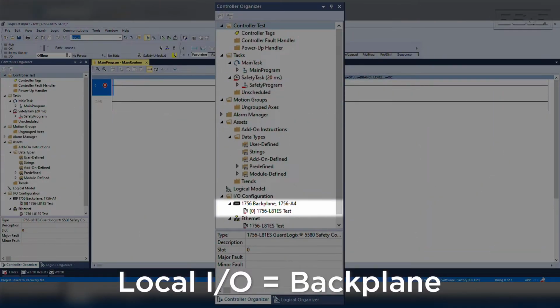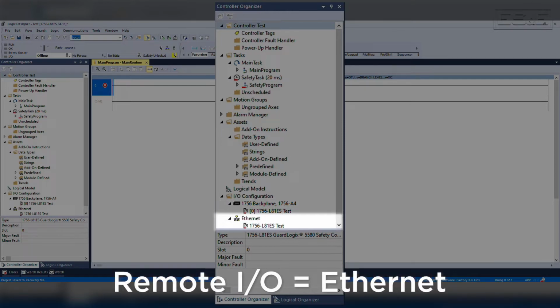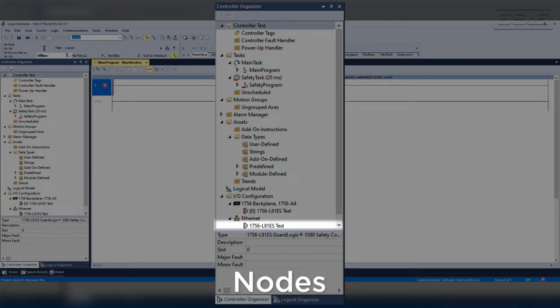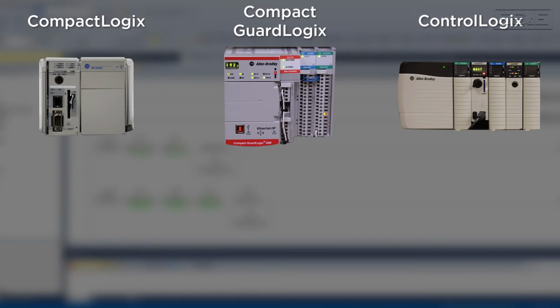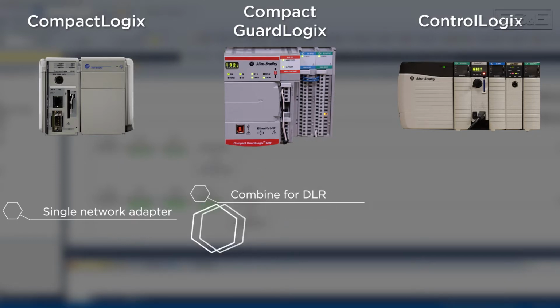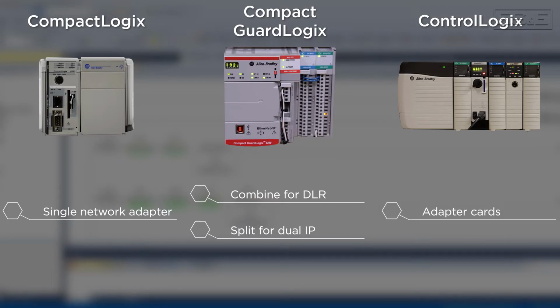Local I/O will always be shown directly connected to the backplane of the controller. In the same backplane, you will also see the additional network adapters that are added for communications to remote devices. Any device added to a communications module is considered a node, and many controllers are limited based on memory size and Ethernet node connections. For 1769 Compact Logix, you will only see one network adapter. For 5069 Compact Logix, you can combine the ports for DLR or you can split for dual IP addresses. Then, for the 1756 ControlLogix, you will see an adapter for each network card added to the chassis.